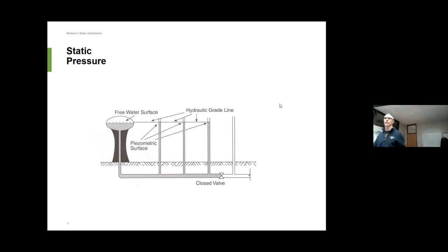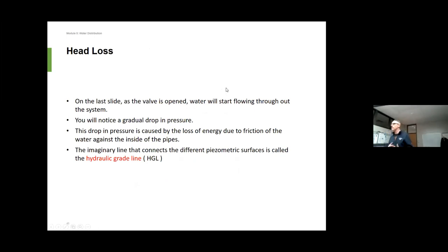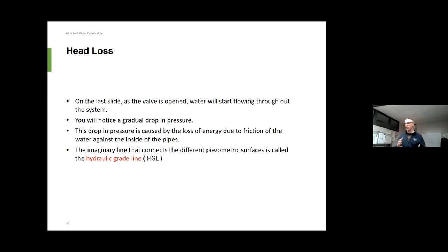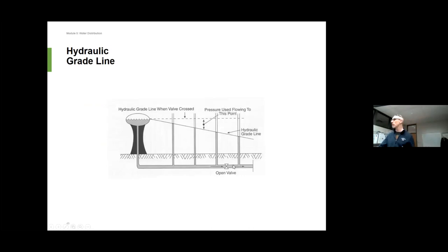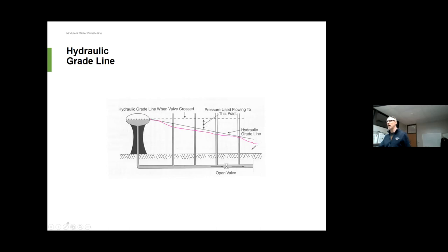What happens when it starts moving? I open that valve and water starts flowing — there's going to be a pressure drop caused by loss of energy due to friction inside your pipe. The walls inside your pipe have friction and slow the water down, causing losses. If there's a valve, a tee, or any time the water changes direction, it's a loss and causes the pressure to drop more and more. Now that the water is flowing, the hydraulic grade line slopes downward — every house further along has less pressure because of those losses.